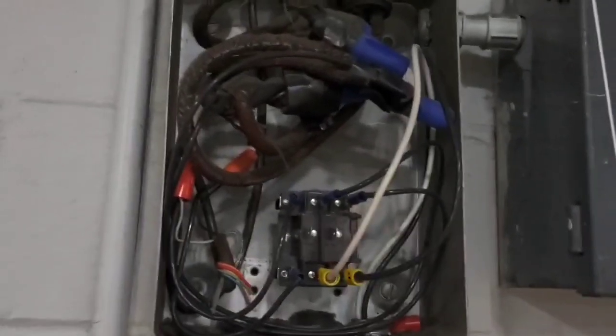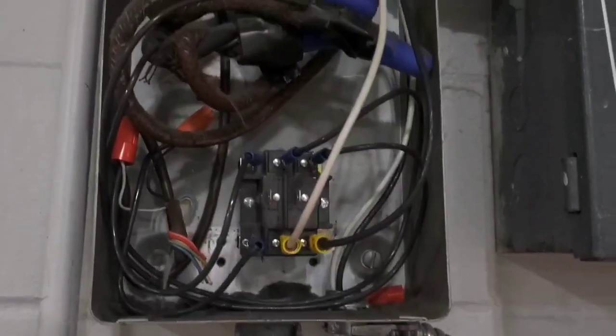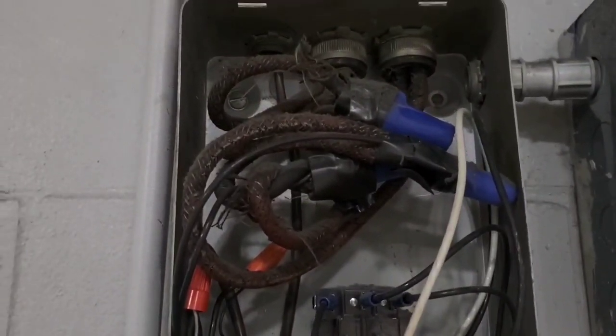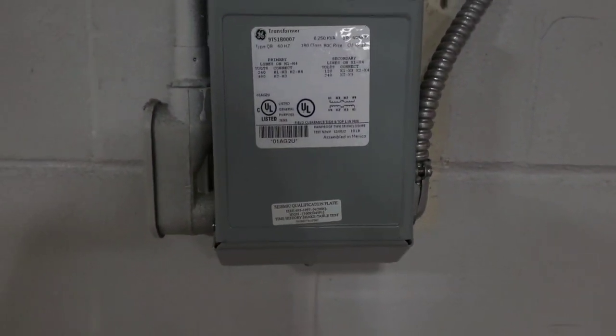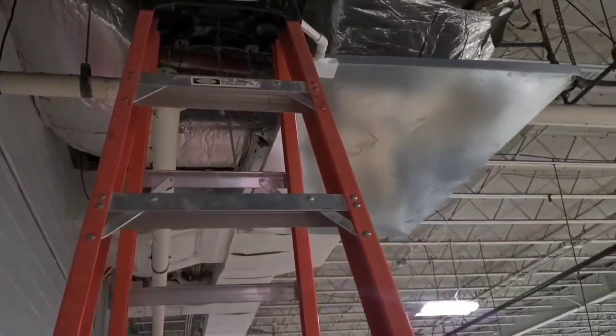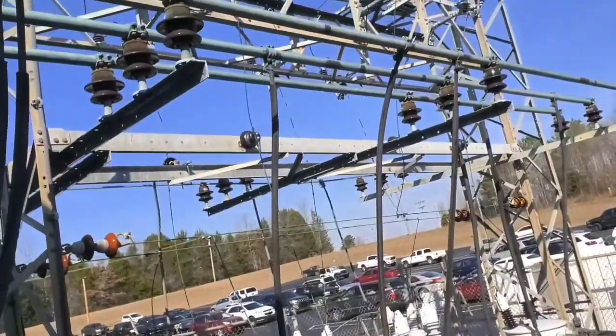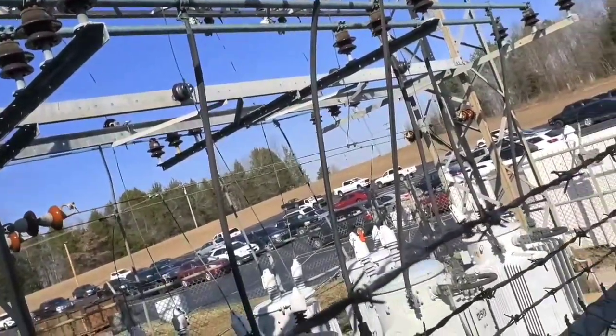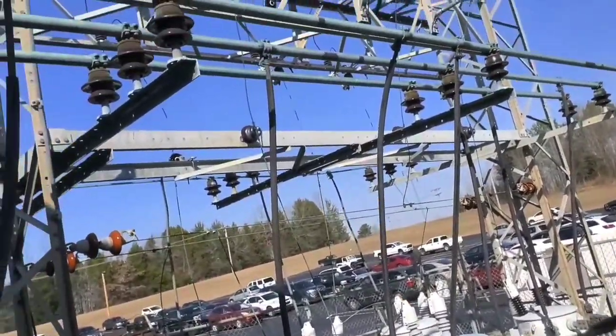So when the thermostat calls for heat, it closes this relay, and that connects 240 volts from those cloth wires down to this step-down transformer. That steps it down to 120 volts, sends it up that conduit, and it powers the heater and its little inducer fan motor. Cloth here too. It's copper, at least, but yeah, if you look closely, there's cloth wire.